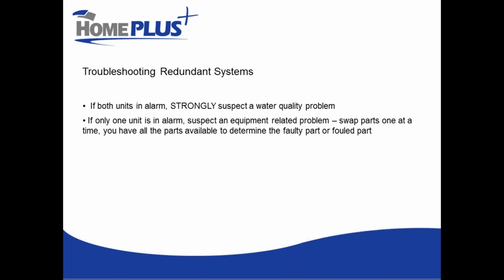If only one of your multiple units is in alarm, you can suspect it's more likely an equipment problem. And you can literally one by one start swapping equipment between your 2 units and use that to identify what component is causing the grief. Now, I would only start swapping components, of course, after I cleaned my sleeve, cleaned my sensor window, and did that proactive maintenance first. But you have all of the components for sure on hand to identify that problem.